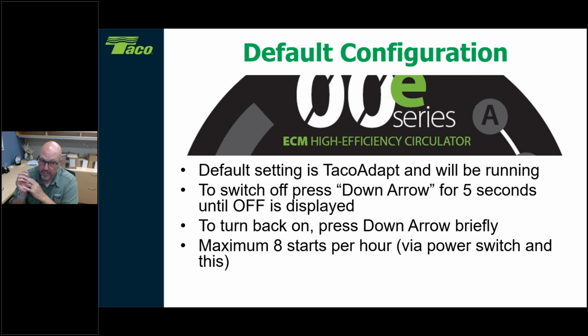Now, this is important. We do not want to power down this circulator more than 8 times in an hour. You could power it down more than 8 times by the faceplate, but you don't want to shut the power down. So we have to be careful. When we're hooking these things up, this circulator can be connected to one of our switching relays that we talked about a couple of weeks ago. But that switching relay kills the power to this, so you don't want to do it.